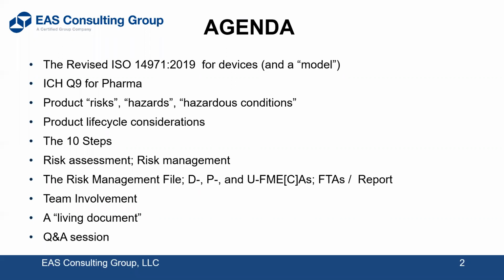Some of you may look at FMEAs and FMECAs and immediately have heartburn because you've heard other consultants say those are not appropriate tools for risk management. I disagree, and we'll talk about that. We'll talk about how we can address some of the complaints raised about an FMEA or FMECA on the outside. But again, I've never had a problem with either a notified body or an FDA inspector on the use of those tools. We'll talk about team involvement and some recommendations I have based on experience, and how the risk management file should be a living document under change control and subject to revision as additional information comes out regarding post-marketing information or industry information as well.